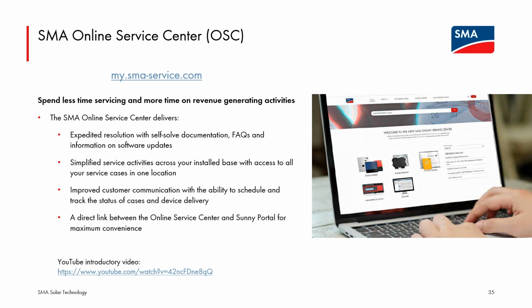Just see one question. I have 2 SMA 50 kilowatt inverters. Do I need overcurrent protection for each inverter, or can I use one fuse disconnect instead? Generally, for systems in the US, there is generally expected to be a separate disconnect and overcurrent protection for each inverter. So I'm not certain what the allowances for not doing that are, but generally you're going to have a disconnect for each inverter. There may be then a massive fuse disconnect for the whole PV system when it's tying into the point of interconnection with building service.